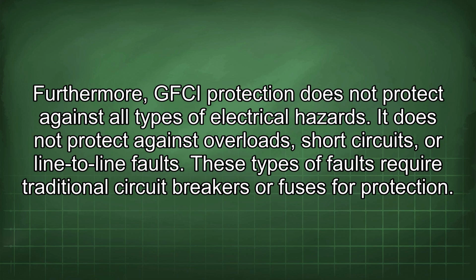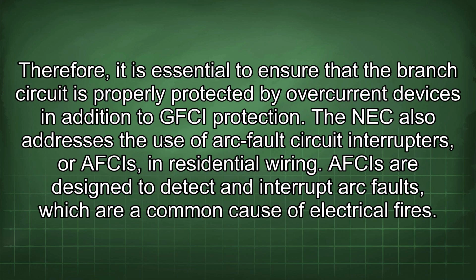Furthermore, GFCI protection does not protect against all types of electrical hazards. It does not protect against overloads, short circuits, or line-to-line faults. These types of faults require traditional circuit breakers or fuses for protection. Therefore, it is essential to ensure that the branch circuit is properly protected by overcurrent devices in addition to GFCI protection.